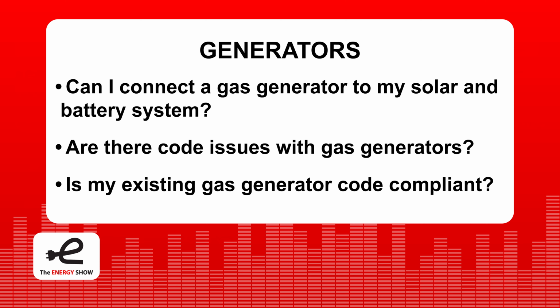If both the solar and the generator are working at the same time, they conflict, both trying to produce power. The generator produces a lot of power because it has a big motor, while solar produces a variable amount depending on sunlight. In almost every case, without careful design and the right automatic switching, they'll conflict. You need to know the exact type and specifications of the generator. We have to scratch our heads when designing a system for someone with a generator. It's tricky.